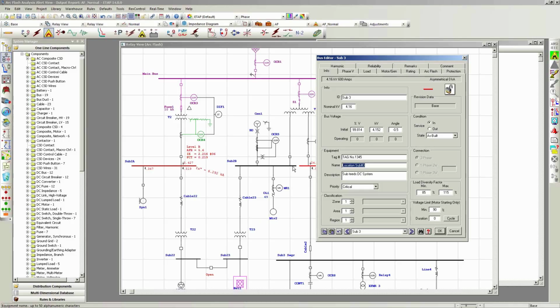a specific substation, and within that substation you have different switchgear lineups, you could be very specific on what the location should be and the description, right? What is this particular bus or switchgear feeding? So all of this really has no impact on your study results, but it does have an impact on your report, meaning when somebody goes out and places all of these labels on the equipment, now they have a little bit more description, right, on what they should be looking for, for example.